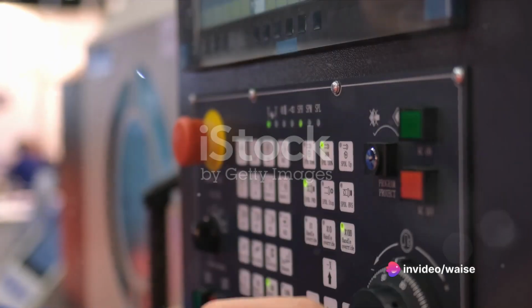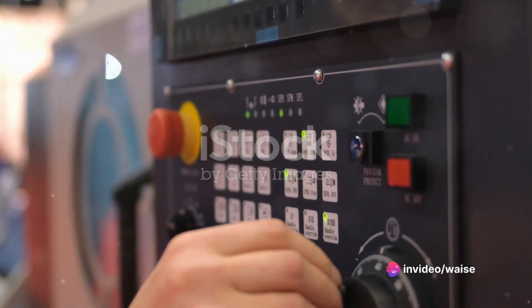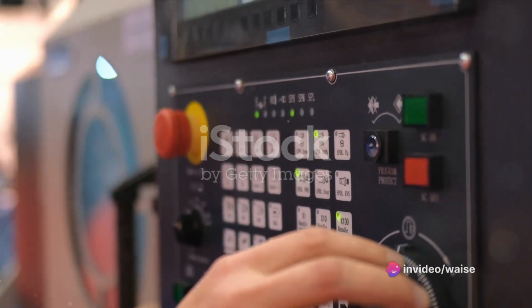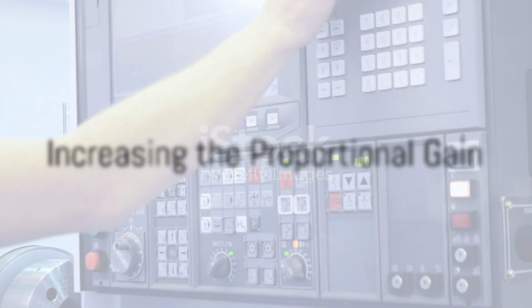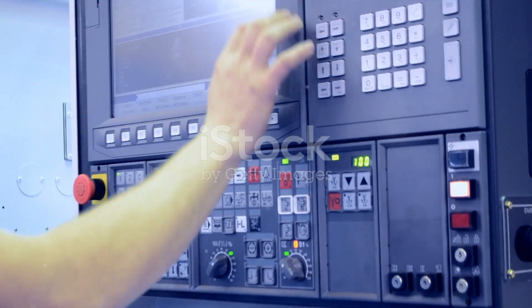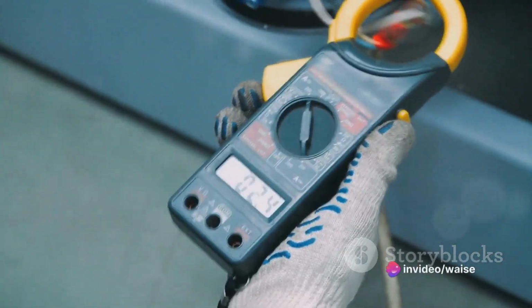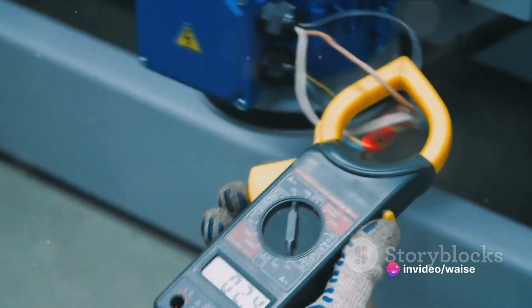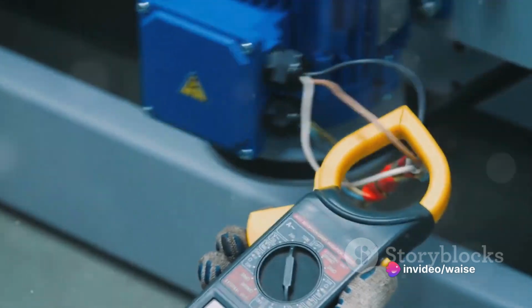Firstly, set the initial parameters. This means setting all three parameters, proportional, integral, derivative, to 0. Next, it's time to increase the proportional gain, or the P gain. This is done gradually until the system starts to oscillate. It's important to note the point where this oscillation begins, as it's a crucial part of the process.